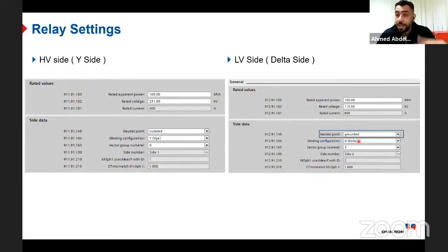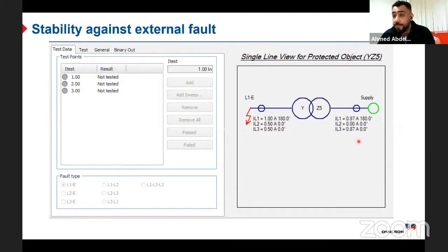So you can do it even in a simple way with the test universe. What are the tests I need to do to confirm that my system is working as per the relay settings? The first one, that you need to confirm that your system is stable against the external fault. So in Omicron, we have what we call a diff configuration module. In the diff configuration module, you have the characteristic of your transformer. You are simulating an external fault on one side, and the fault is supplied from the other side. You need to confirm that your system is stable in this case or not.